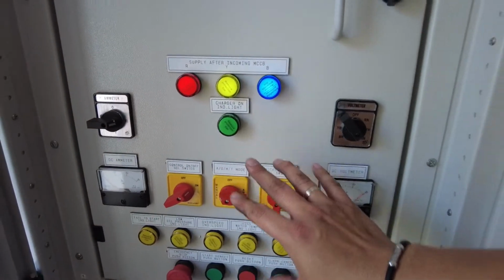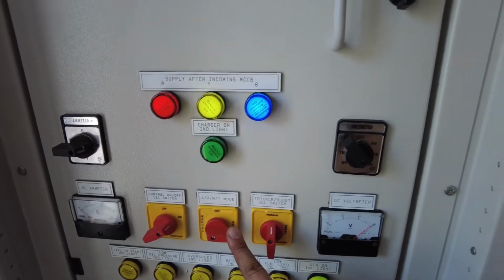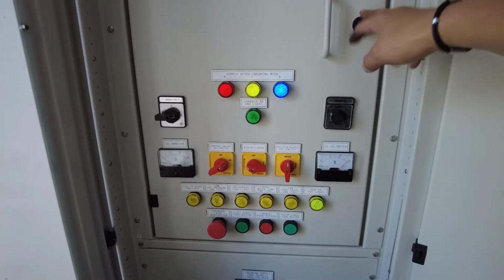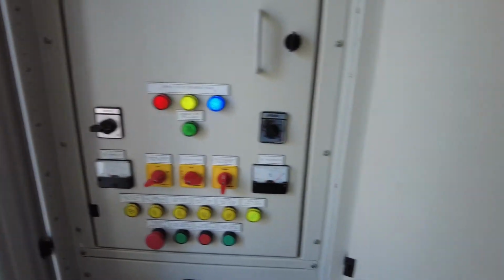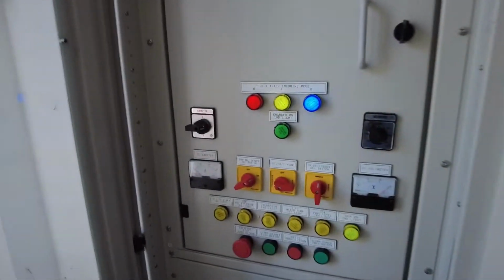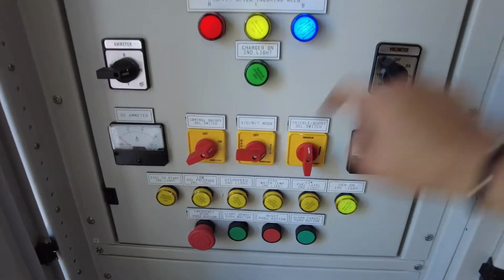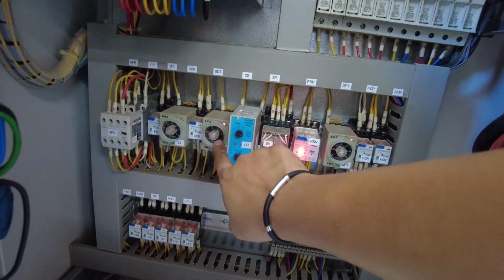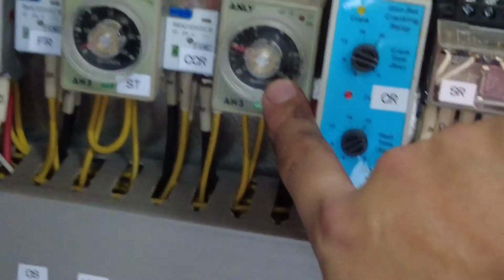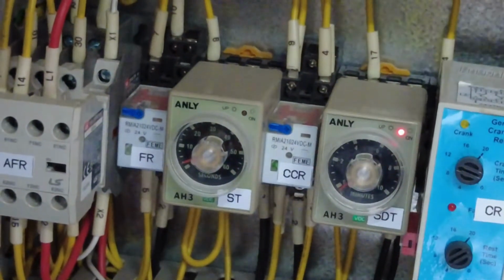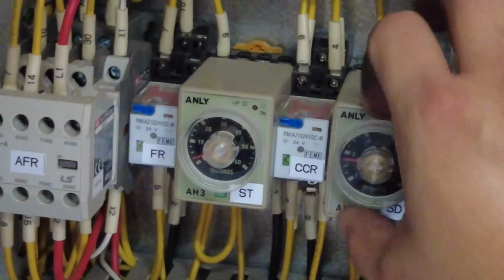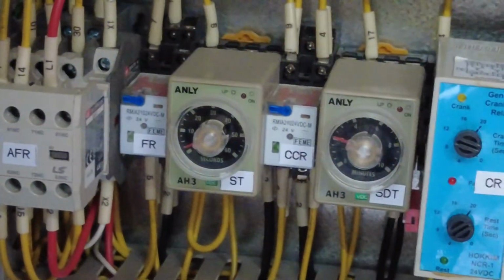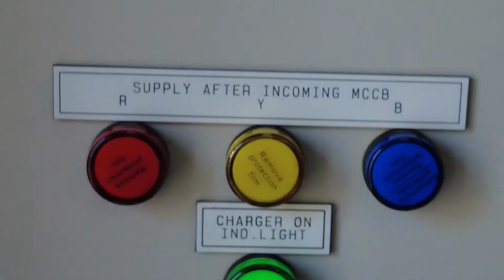We allow it to run for 1 minute. Then we put it back to auto. Then we activate the shutdown timer to stop the genset. Okay, now we put to auto. Now it's under auto, but the genset is still running because the shutdown timer is not activated yet. Now I'm going to activate the shutdown timer. Okay. Now the shutdown timer is activated, genset stop. Okay, now the genset is already stopped.